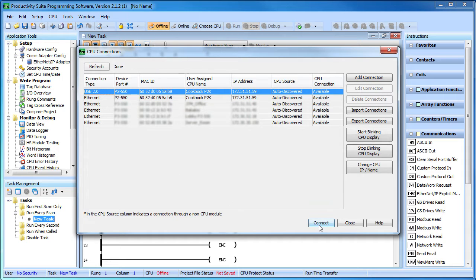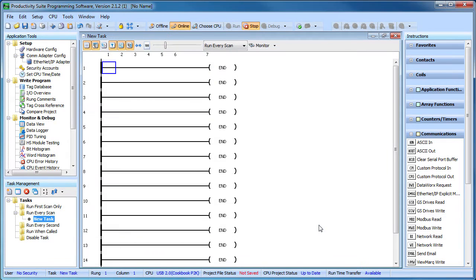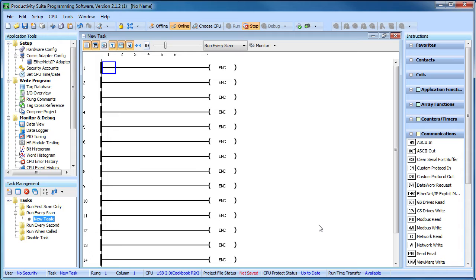The beauty of the USB connection is you can program the controller independent of the IP address. And since you aren't using the Ethernet port to connect, you can set the controller's IP address to be compatible with whatever network this controller will ultimately end up in.